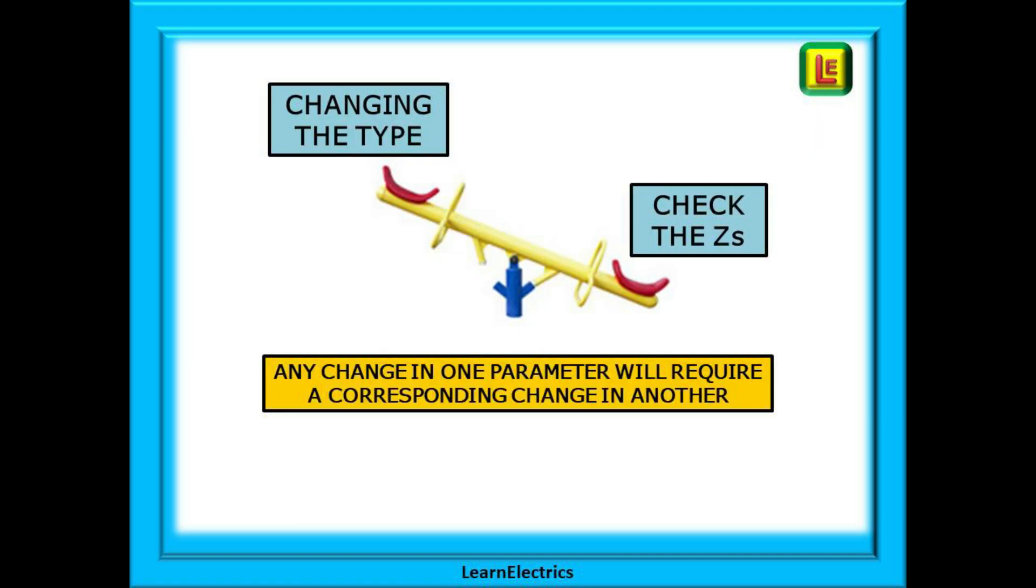Always be aware that if you are planning to change the type of breaker then you must check the ZS first. If the ZS is not suitable for the new MCB then you must take steps to reduce the ZS before fitting the new MCB. The ZS and the MCB requirements must match each other.